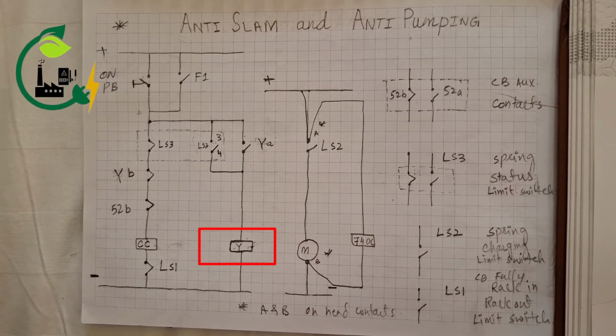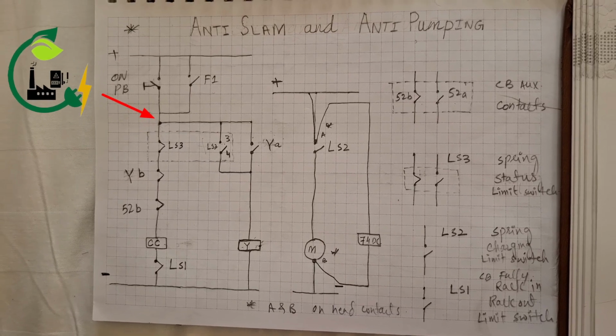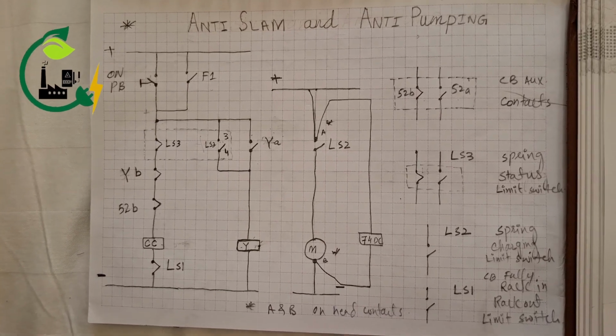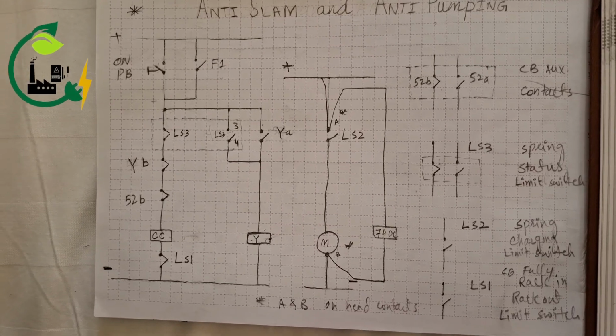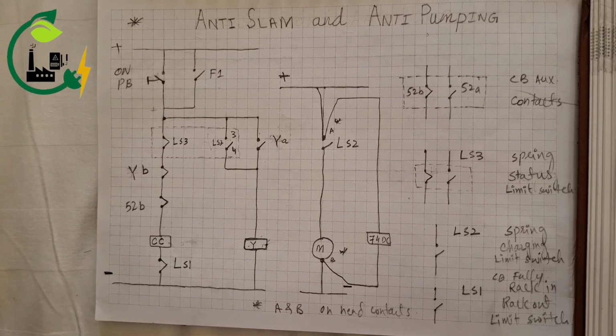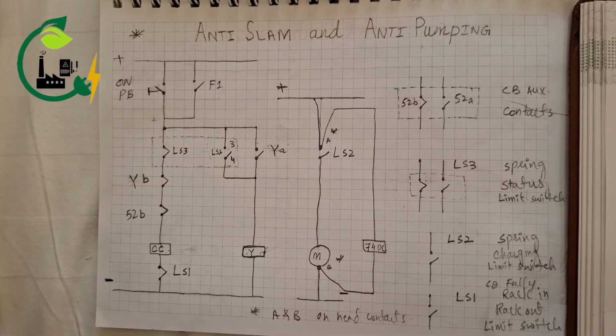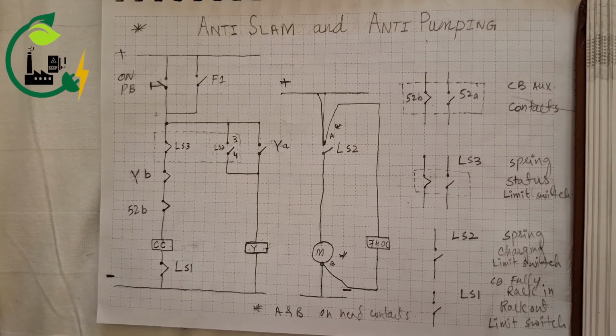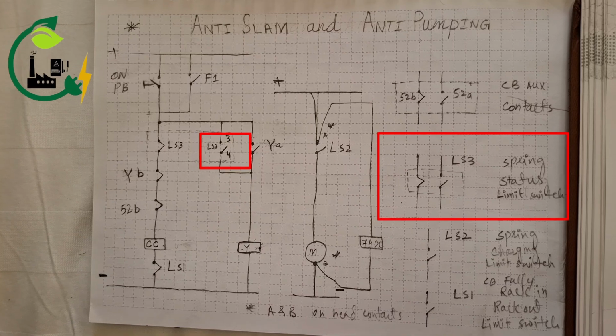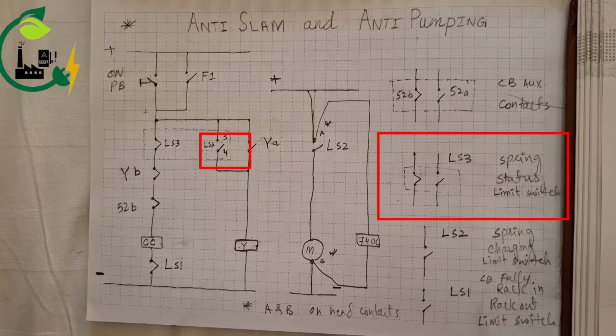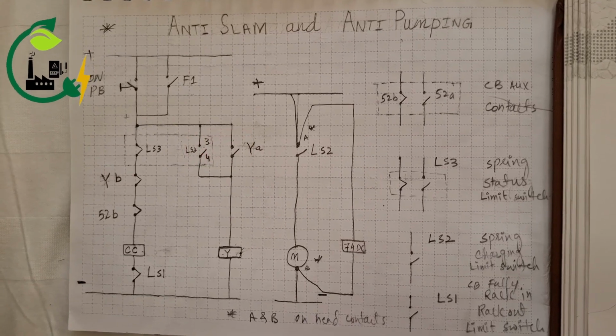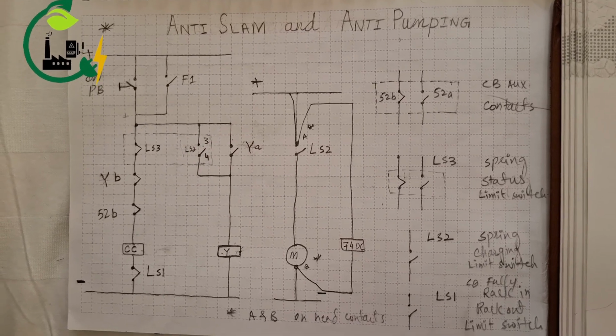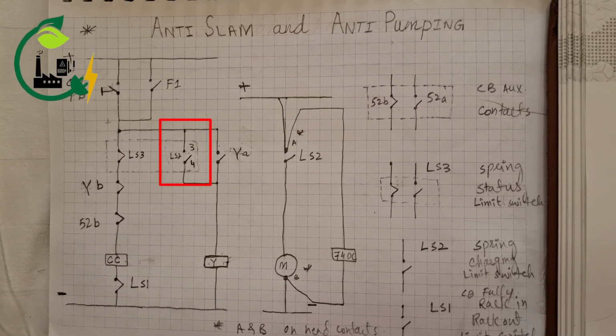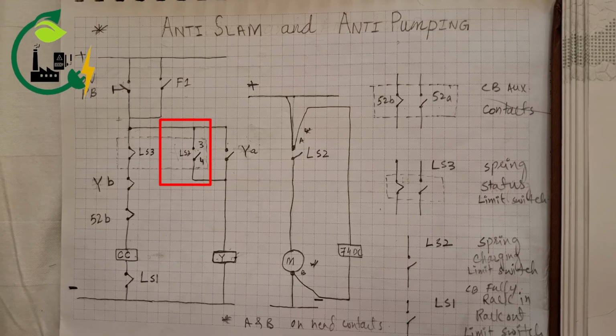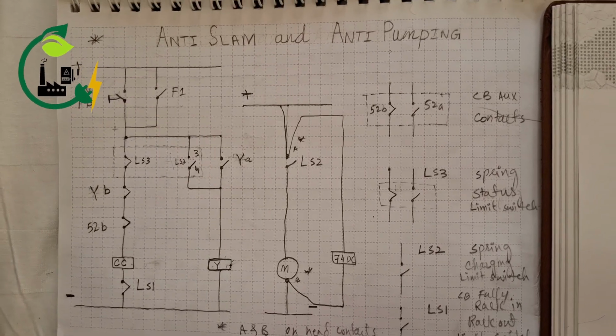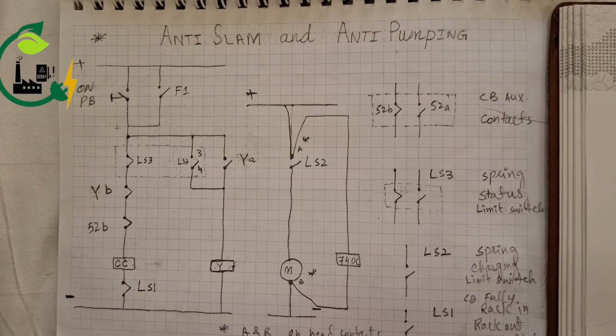How does the anti-pumping relay work? We take the supply from this point and give it to the anti-pumping relay, but we have to operate the anti-pumping relay once we give the command to the circuit breaker. The first command goes to the coil, and then it prevents the command from going to the circuit breaker again and again. How does it work? We use the limit switch from the spring. Sometimes we can also use the auxiliary contact of the circuit breaker, but here we use the spring status limit switch LS3 contact. The LS3 3-4 contact we use for the anti-pumping, and the LS3 1-2 contact also protects the closing coil.